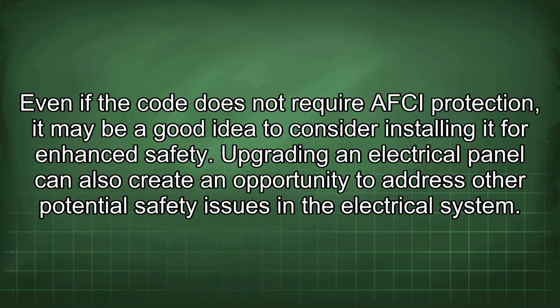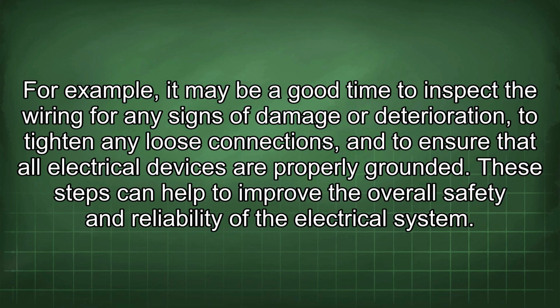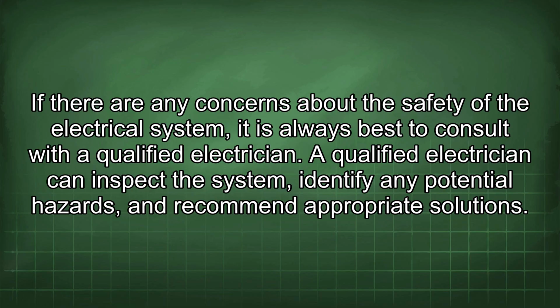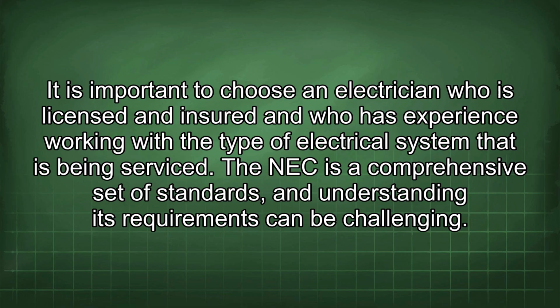Even if the code does not require AFCI protection, it may be a good idea to consider installing it for enhanced safety. Upgrading an electrical panel can also create an opportunity to address other potential safety issues in the electrical system. For example, it may be a good time to inspect the wiring for any signs of damage or deterioration, to tighten any loose connections, and to ensure that all electrical devices are properly grounded. These steps can help to improve the overall safety and reliability of the electrical system. If there are any concerns about the safety of the electrical system, it is always best to consult with a qualified electrician. A qualified electrician can inspect the system, identify any potential hazards, and recommend appropriate solutions. It is important to choose an electrician who is licensed and insured and who has experience working with the type of electrical system that is being serviced.